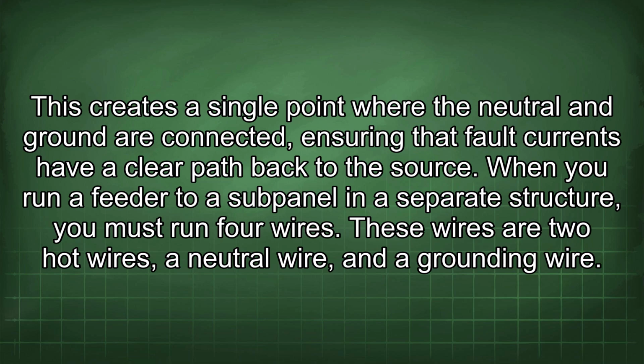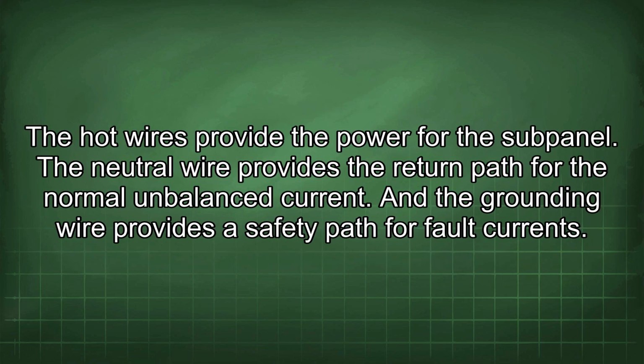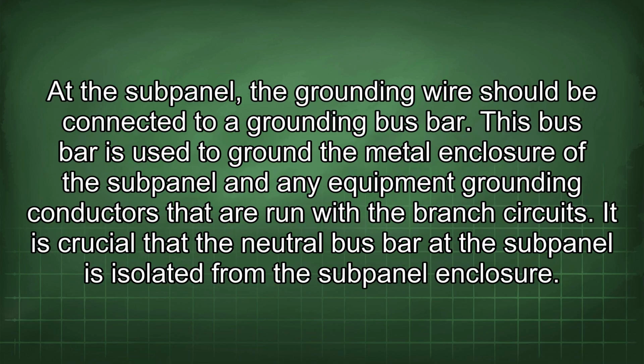When you run a feeder to a subpanel in a separate structure, you must run 4 wires. These wires are 2 hot wires, a neutral wire, and a grounding wire. The hot wires provide the power for the subpanel. The neutral wire provides the return path for the normal unbalanced current, and the grounding wire provides the safety path for fault currents. At the subpanel, the grounding wire should be connected to a grounding bus bar. This bus bar is used to ground the metal enclosure of the subpanel and any equipment grounding conductors that are run with the branch circuits.